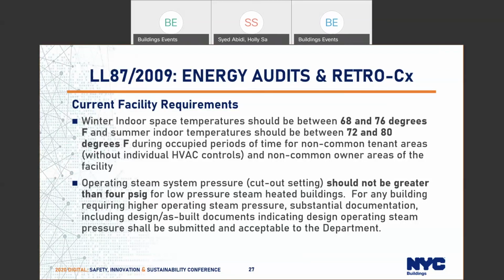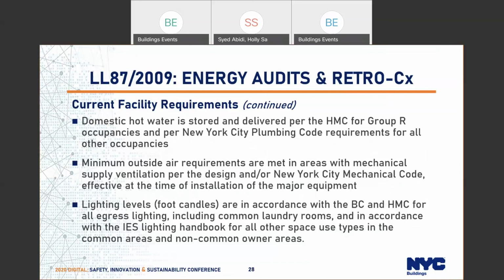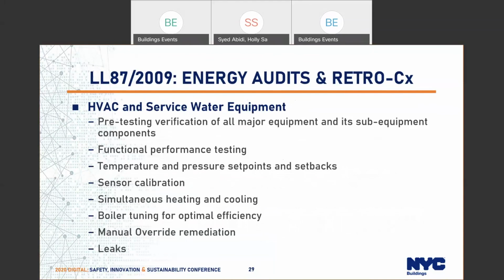Current facility requirements cover indoor space temperatures, operating system pressure for low pressure steam heated buildings, domestic hot water storage and delivery temperatures, ventilation rates, lighting levels. Rule amendments also now cover HVAC and service water equipment in detail by defining pre-testing verification of all major equipment and its sub-equipment and components. It goes deeper into the functional performance testing requirements, temperature and pressure set points and setback, sensor calibration, simultaneous heating and cooling, boiler tuning for optimal efficiency, manual override remediation, and leaks.